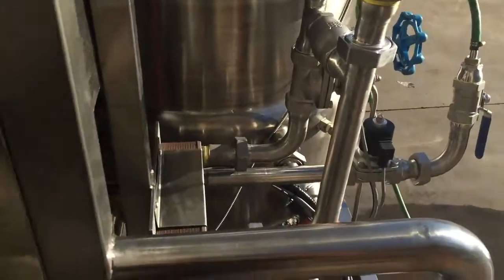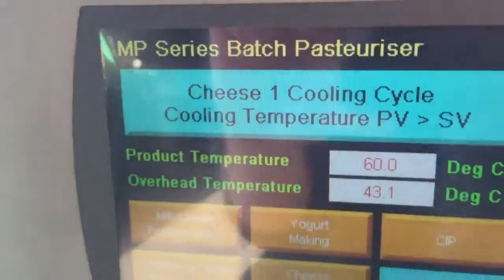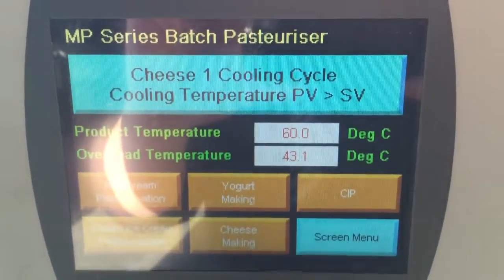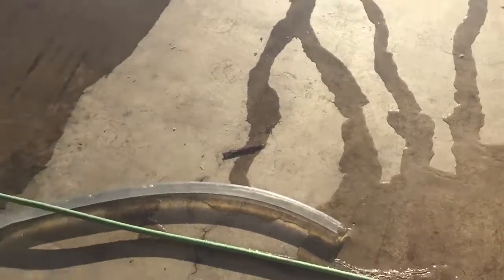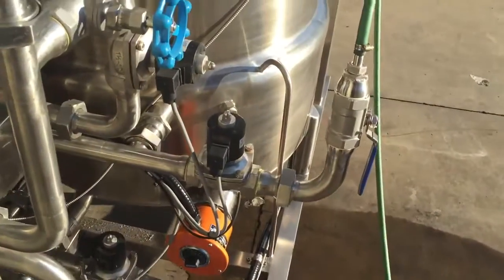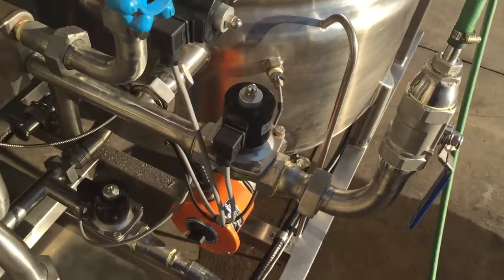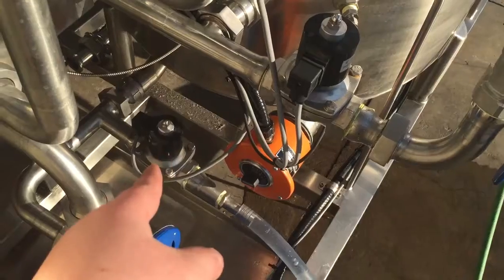Holding time finished. The system will drain the water through the jacket, and now we are doing the cooling. The cold water will fill through the jacket and come out from the drain valve. This is the cold water inlet valve, and that is the drain valve.